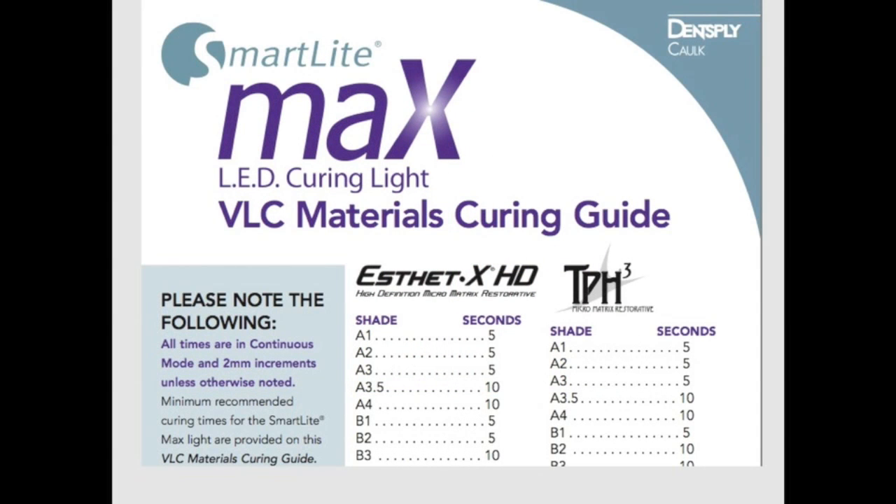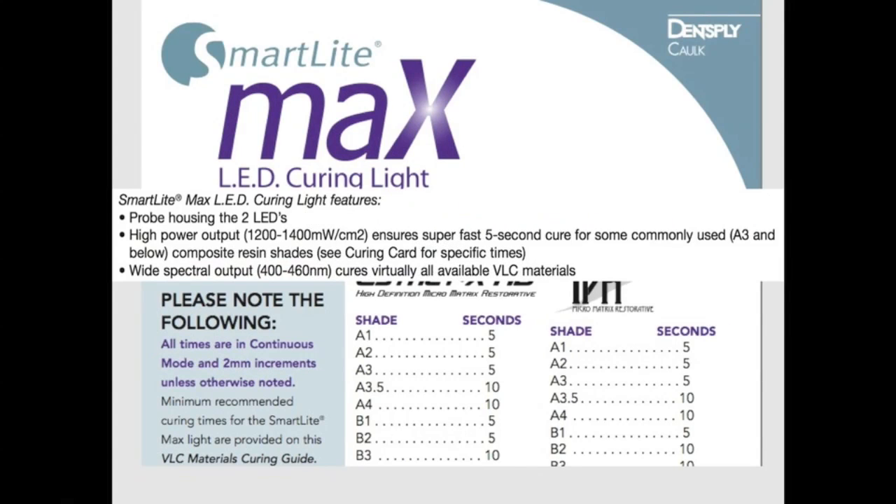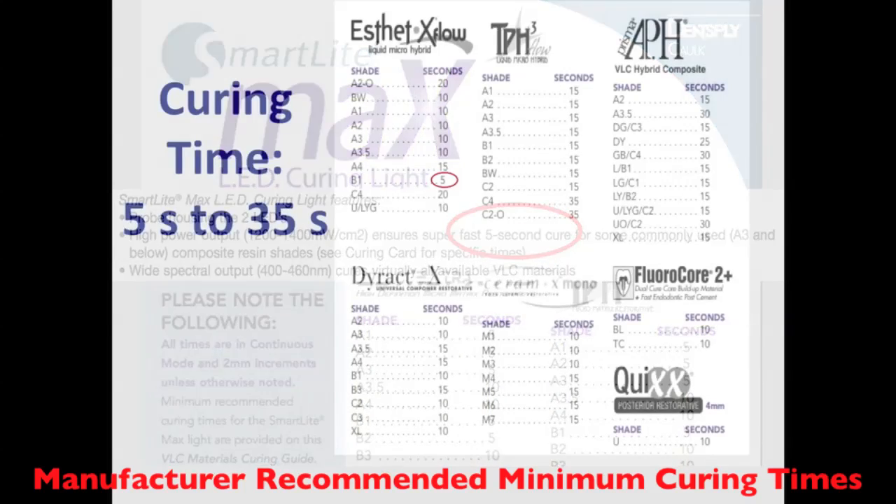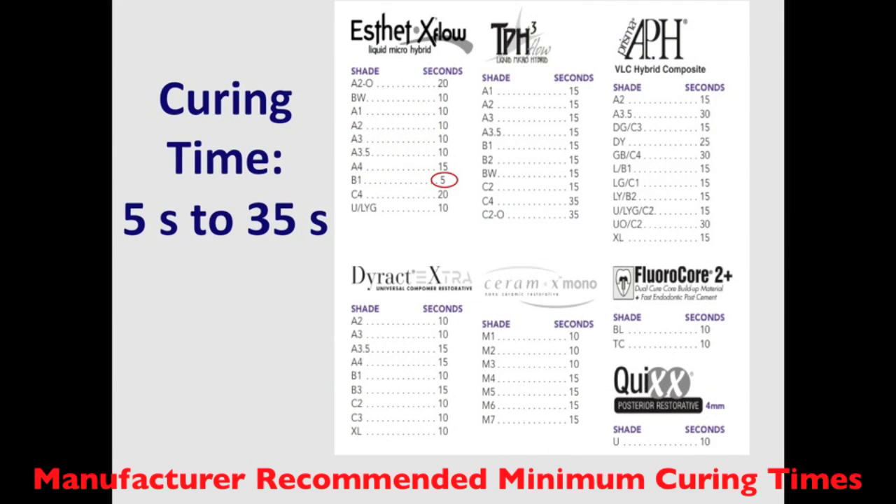Here we can see a slide of the SmartLite Max LED curing light, which claims fast 5-second curing times for some commonly used materials. Turning to the back side of this sheet, yes, that's true for Esthet-X flow — B1 shade requires 5 seconds. But at the other end of the scale, TPH shade C4 requires 35 seconds. That's a 7-fold increase in curing time, and dentists need to be aware of these huge ranges in curing times for composites made by the same resin manufacturer.